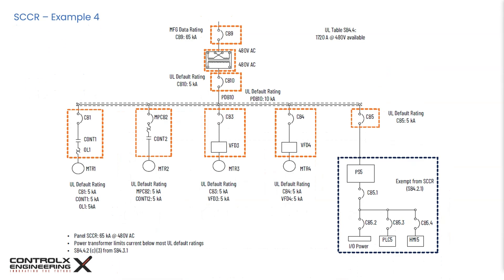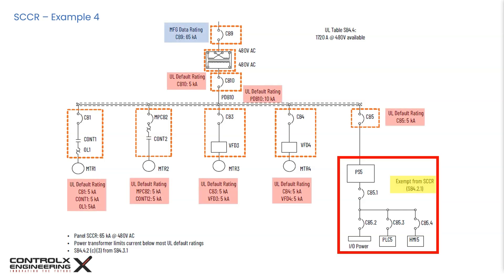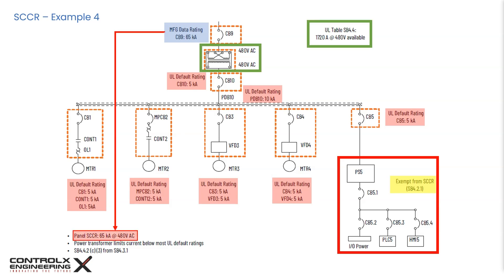The fourth example involves an isolation transformer. The main circuit breaker CB9 has a rating of 65 kA, and all components on the transformer secondary have lower SCCR values. Since the transformer limits the current to 1.7 kA at 480V — below most device ratings — the panel SCCR in this example is 65 kA.